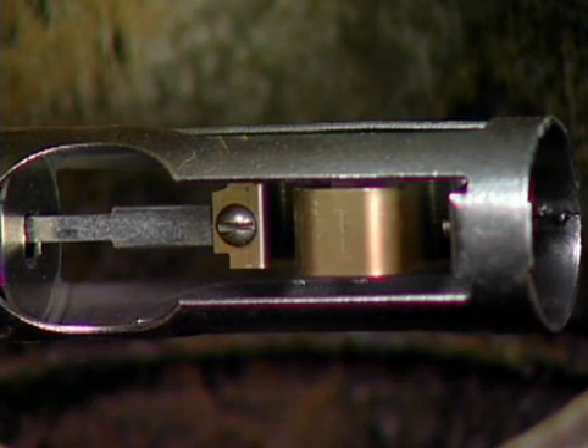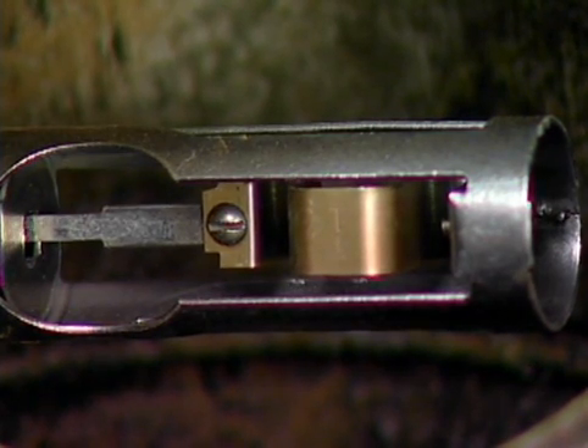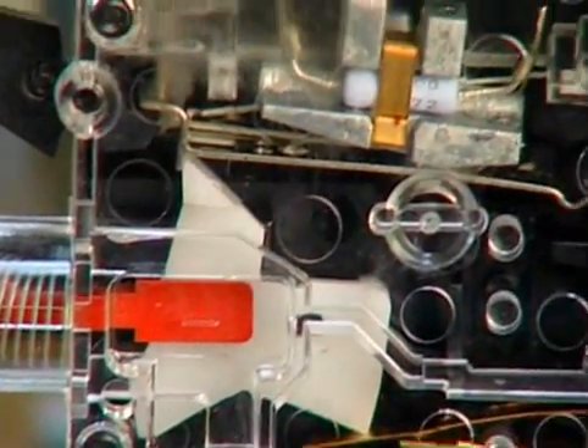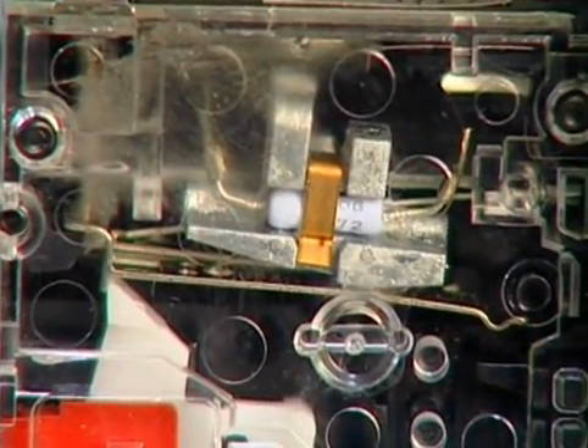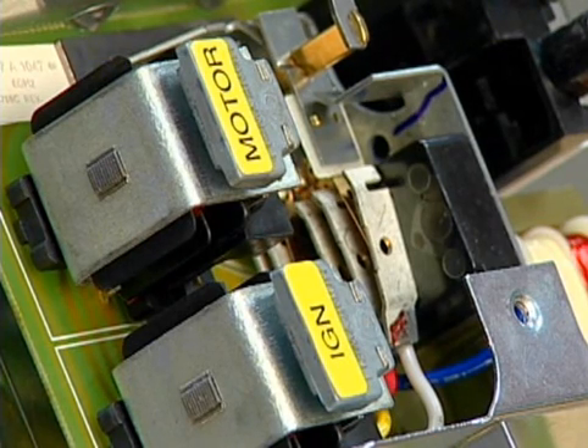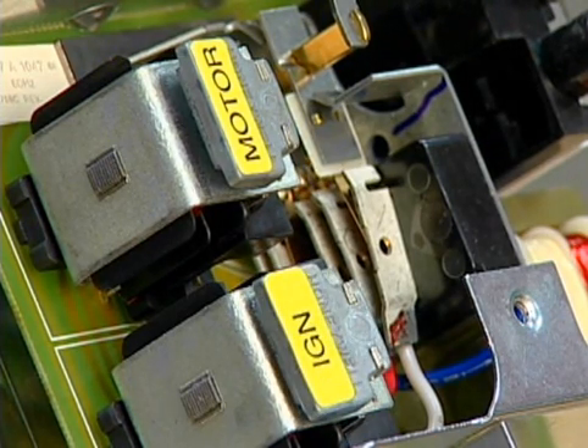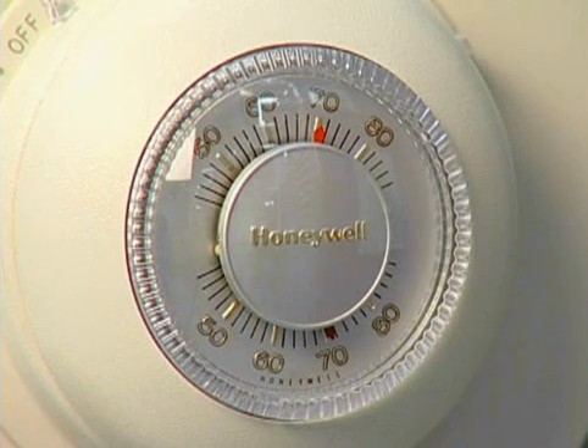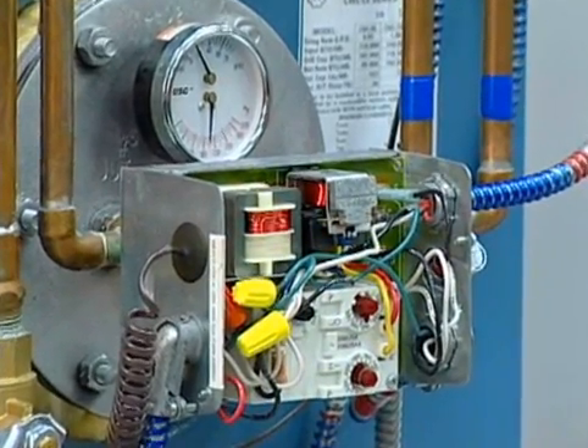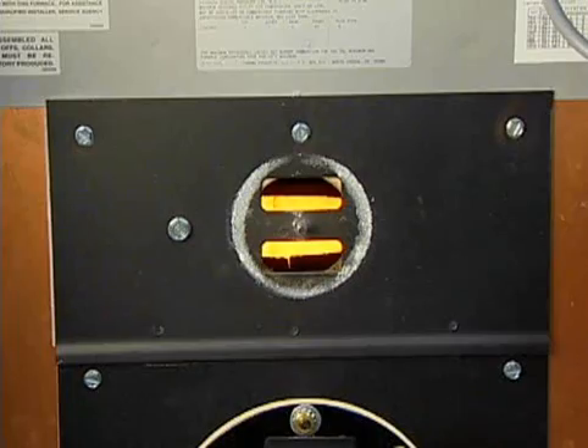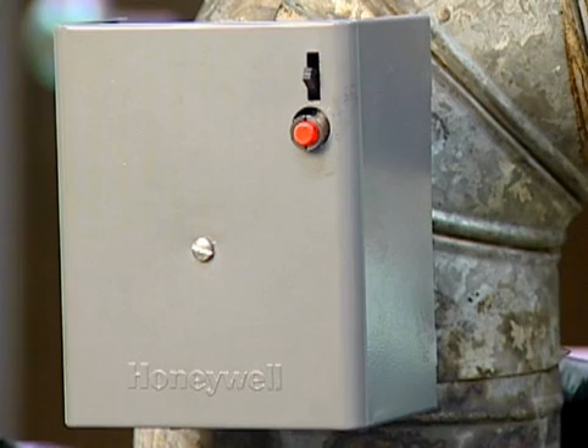Once flame is established and heated flue gases pass over and expand the bimetal detector element, the safety switch heater will be de-energized, preventing the unit from shutting off on safety. The ignition circuit will be de-energized, shutting off the transformer if the unit operates on interrupted ignition. The oil burner will then continue to run until either the thermostat is satisfied, opening the low voltage circuit, or the limit control is satisfied, opening the line voltage circuit. Either of these actions causes the primary control to cut power to terminals 3 and 4, safely shutting down the oil burner. The primary control then returns to standby mode.